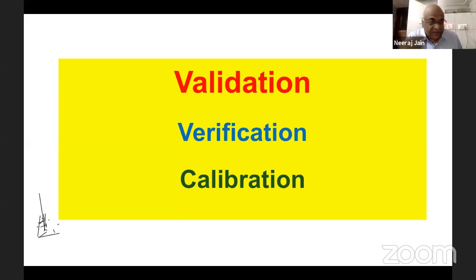Calibration is the method of ensuring the desired performance of equipment. There are various ways of calibrating the equipment. For non-analytical instruments, we take the help of some calibration lab which is accredited for the calibration of that particular equipment, as per ISO 17025, because that is the document for all testing and calibration laboratories. And all your analytical instruments are calibrated by the manufacturers.